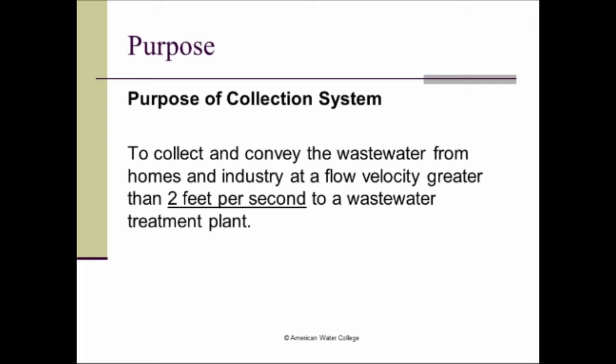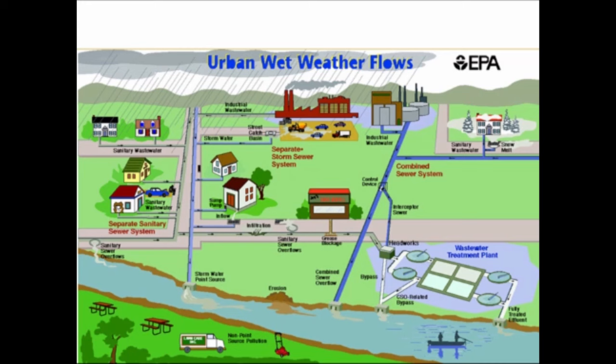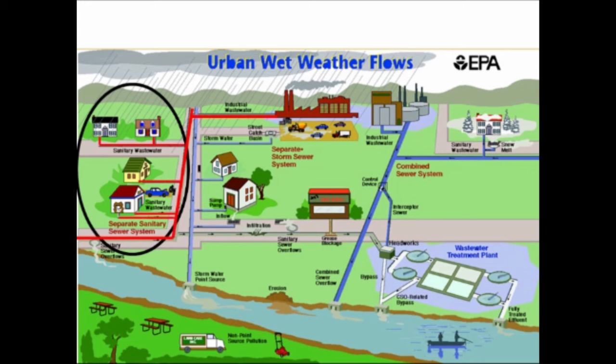The purpose of a collection system is to collect and convey the wastewater from homes and industry at a flow rate greater than two feet per second to a wastewater treatment plant. The system is designed so that flow is at least two feet per second, collecting water from both residences and commercial and industrial customers. Industry and residences combine to provide all the flow that goes to the headworks of the wastewater treatment plant.